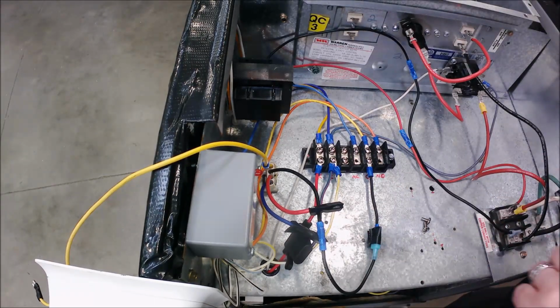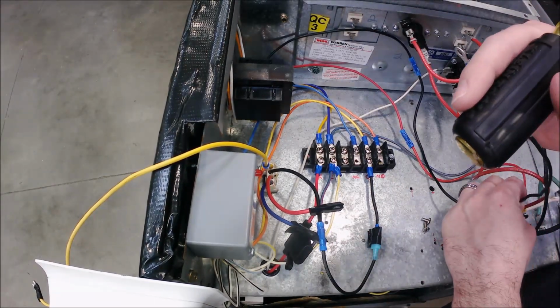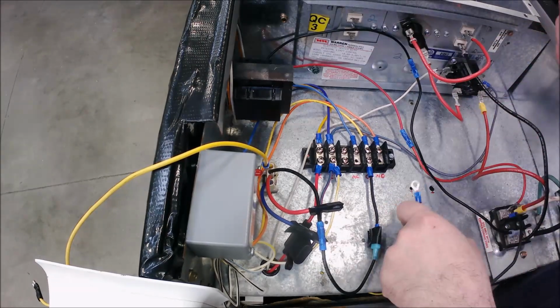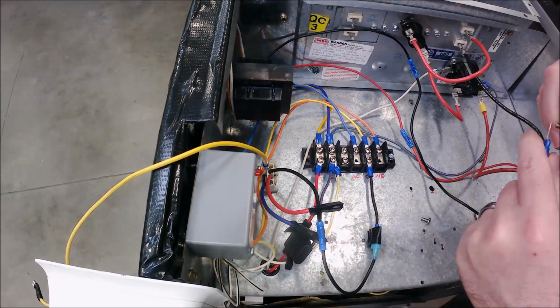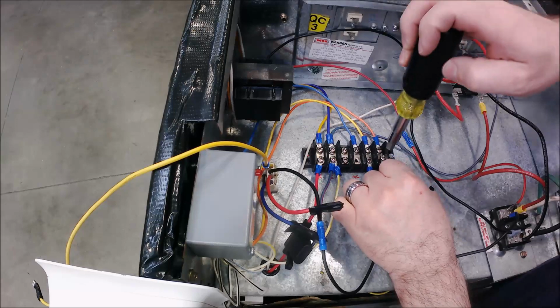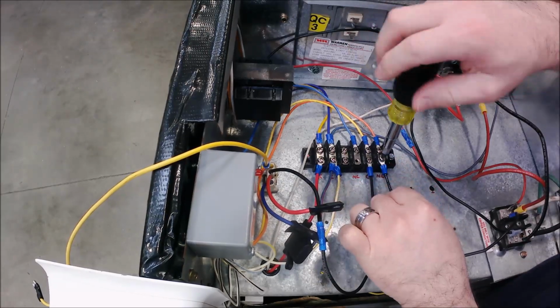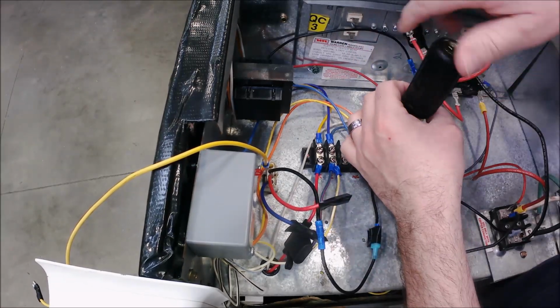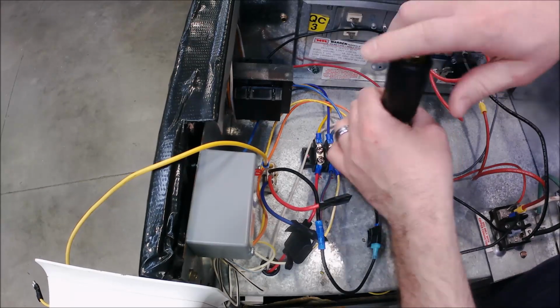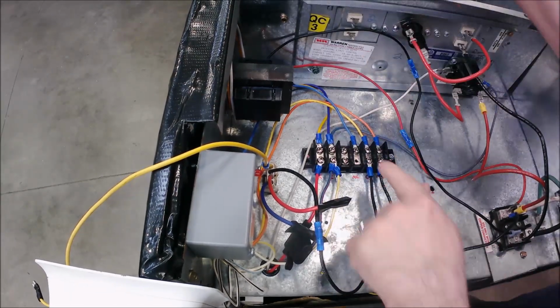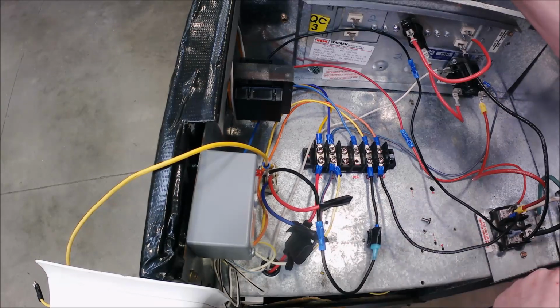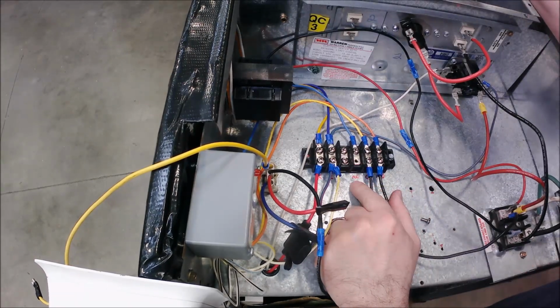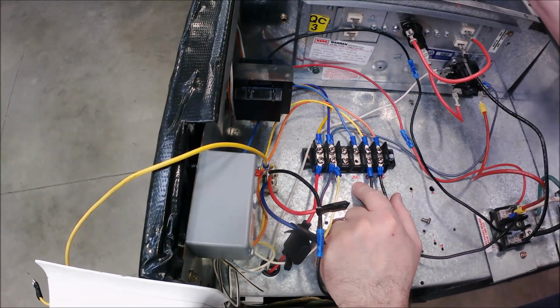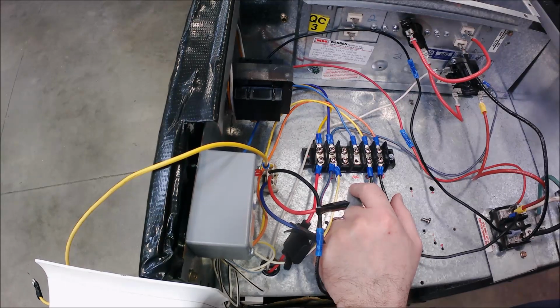L1 comes from over here on the terminal block. I'm going to put straight L1 power on that connection into the normally open switch. When I get a call for cool or for fan, it'll come out of the common. Alright? A lot of guys get messed up on this normally closed connection. Where do we get it and what's it for?